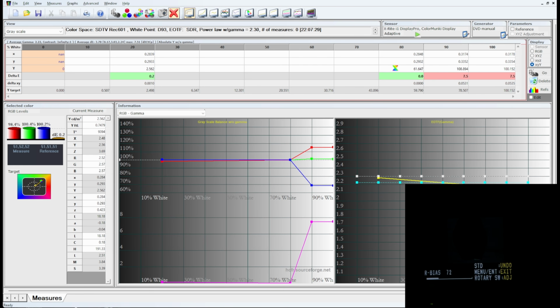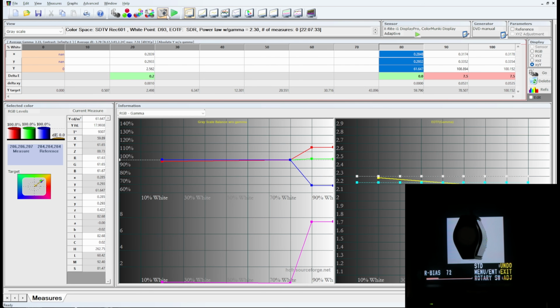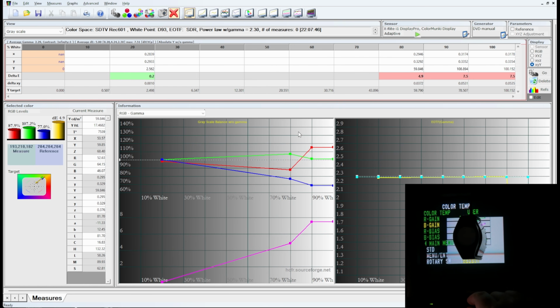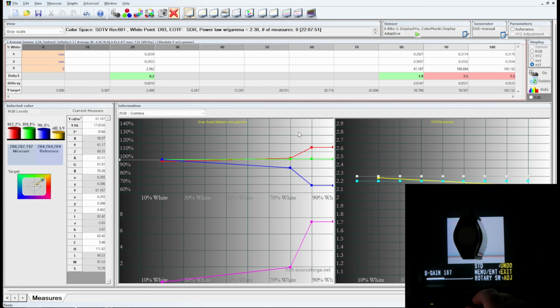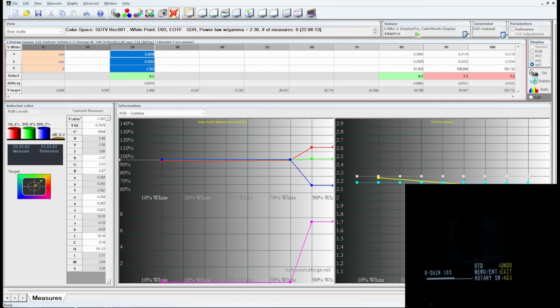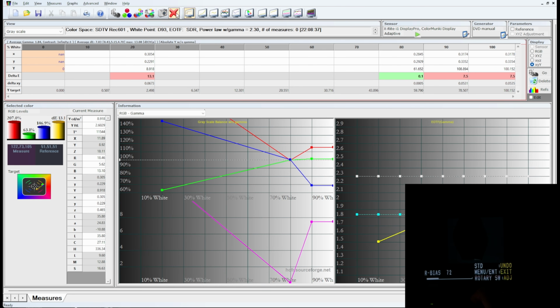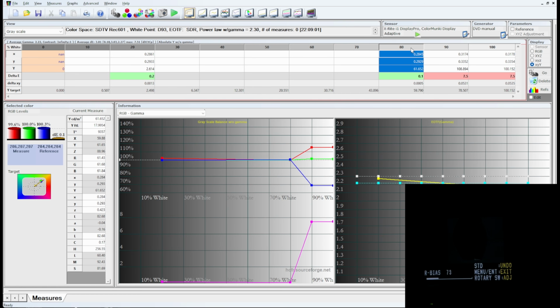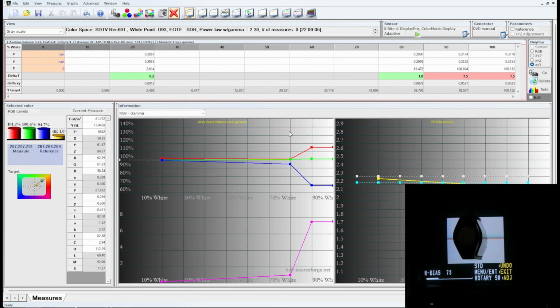Let's go back to 80 IRE because all of these numbers are now going to have changed. So here we are at 80 IRE, and now my colors are off again. I'm still under 2.0, which is good, but we can make this better. And now I'm going to stop scanning, and we're going to go back to 20. Stop the test, back, and you just go back and forth, and we keep doing this, back and forth.